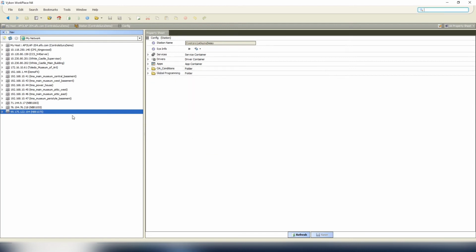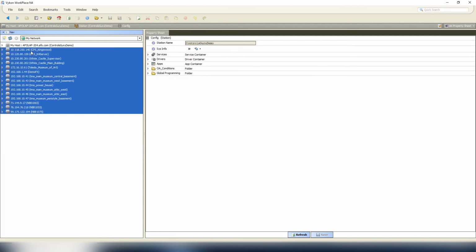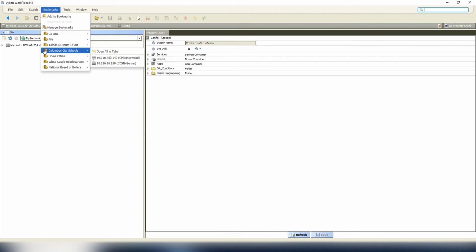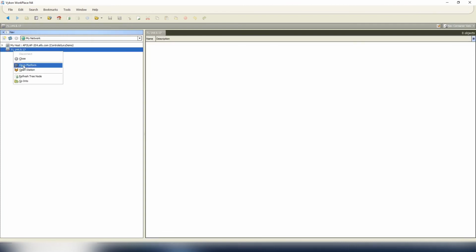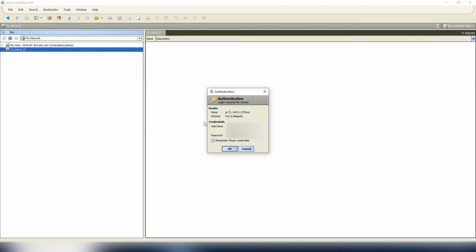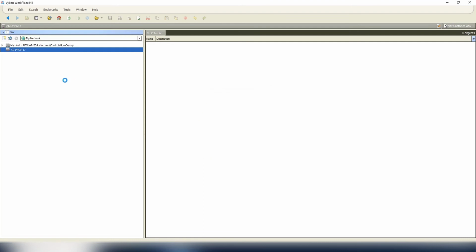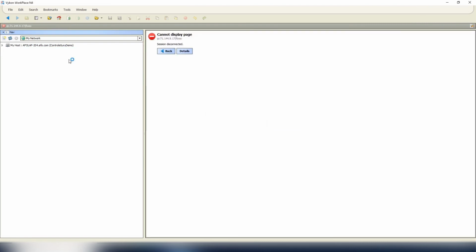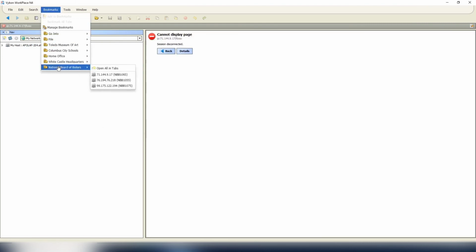Hit OK. And then what I can do here is you can actually close out of all of these 15 hosts. Now you're cleared up over here on your nav tree, but if you go into your bookmarks, you've got all of the Jaces and everything right here. So if you wanted to access one of them, you would just go to it, and then open the station. And then it's going to ask you for your information. And there you go. So this way, you can close out of them when you're done with them if you're not regularly accessing them, and then you'll always have them within your bookmarks.